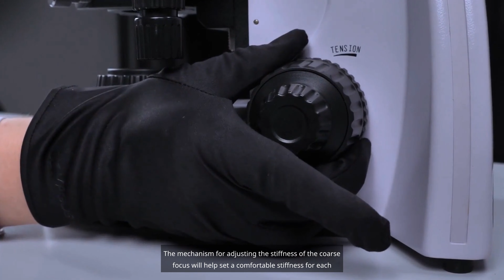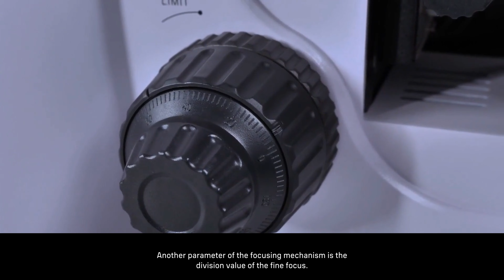The mechanism for adjusting the stiffness of the coarse focus will help set a comfortable stiffness for each user. Another parameter of the focusing mechanism is the division value of the fine focus. On our microscope, it is 2 microns. This step is optimal for a student and routine microscope, as it provides both accuracy and speed of focusing.